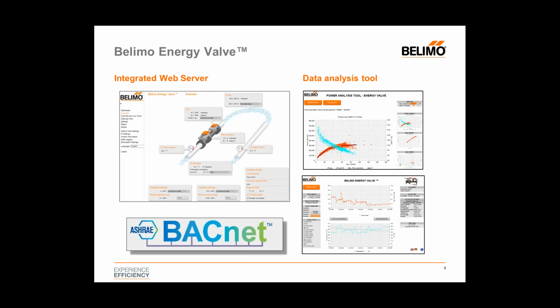Now, as we talked about earlier, the energy valve actuator has a data logger built into it, and it stores up to 13 months of the data points that I just talked about: flow, power, valve position, supply and return water temperature, heating and cooling energy, just to name a few. And what we provide free of charge is a data analysis tool. You can export that data out of the actuator, which comes out in a comma-separated value file, and import it into the data analysis tool. The data analysis tool is simply a macro to align all the column headings and bring it right into the tool, so you can look at it all in a graphical representation. So you can see graphically what's going on within your system.